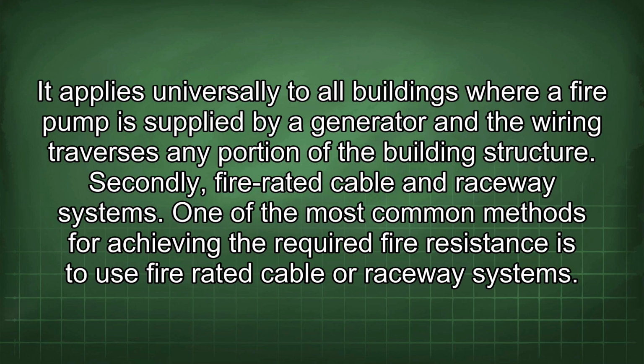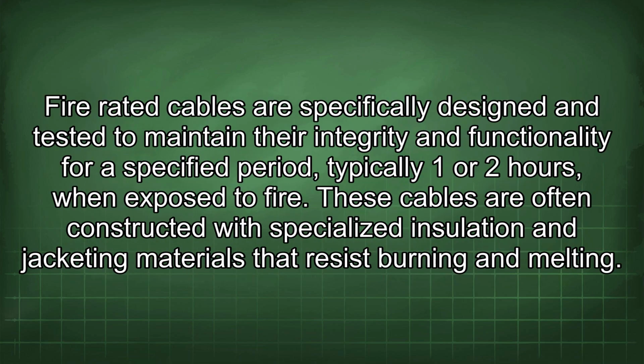Secondly, fire-rated cable and raceway systems. One of the most common methods for achieving the required fire resistance is to use fire-rated cable or raceway systems. Fire-rated cables are specifically designed and tested to maintain their integrity and functionality for a specified period, typically 1 or 2 hours, when exposed to fire. These cables are often constructed with specialized insulation and jacketing materials that resist burning and melting.